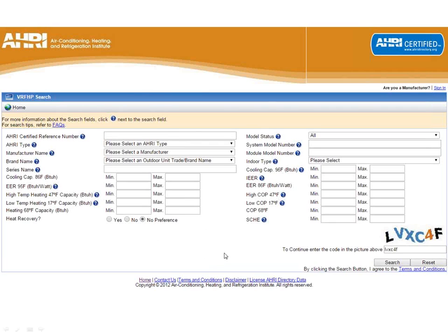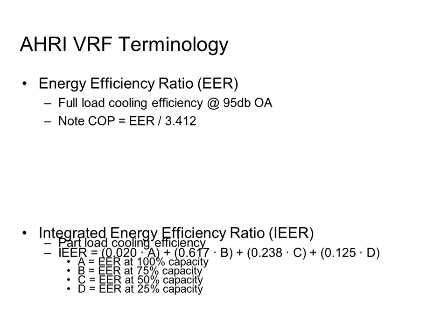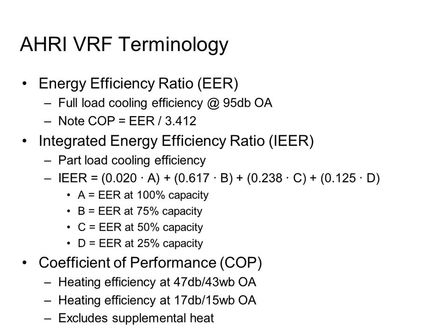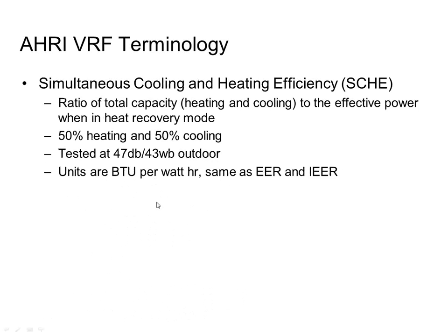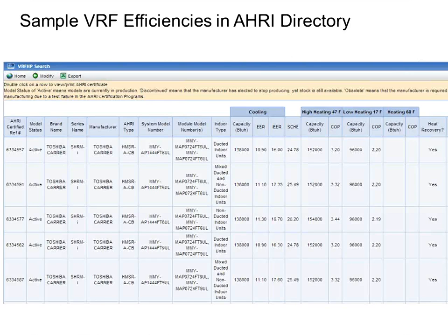But really, as you're going to see in a little bit, that doesn't correlate to all equipment. It's either 95 or 86, depending on what type of equipment it is, air or water. So you cannot get it from AHRI. They don't give you the individual values of these 4 testing points on the IEER, but your manufacturer may be able to get it to you. We'll also talk a little bit about simulation tools in a couple minutes here.